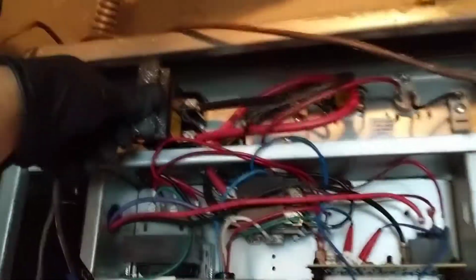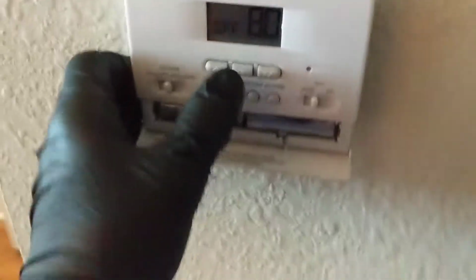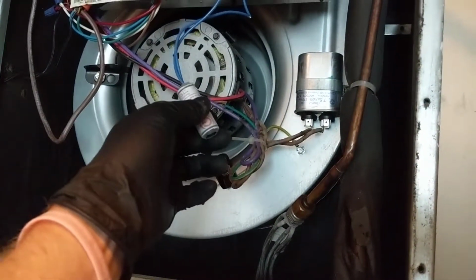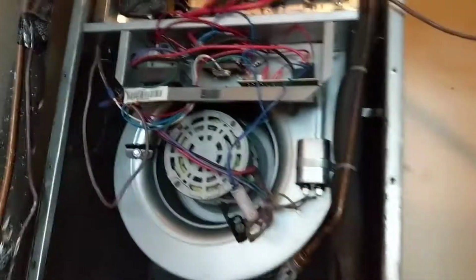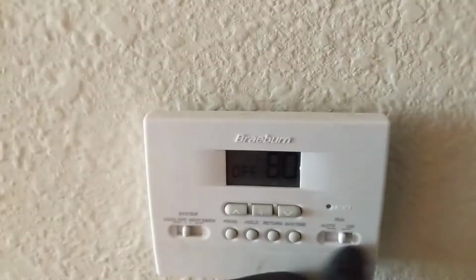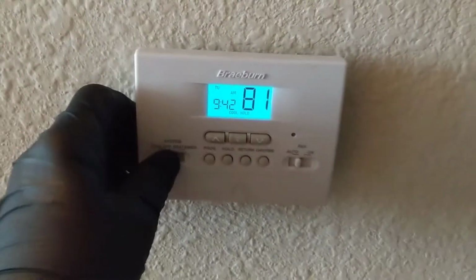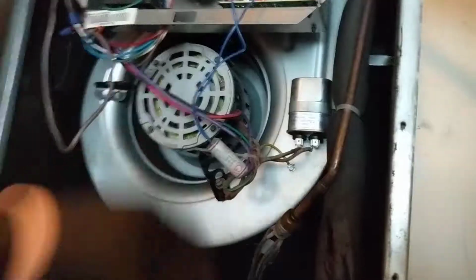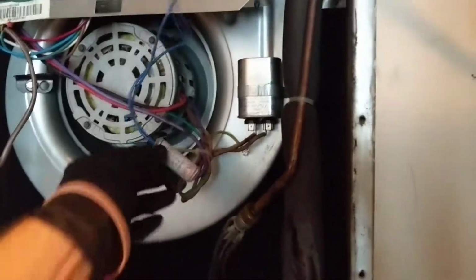Let's throw the power back in and put the thermostat back on and see what we got here. Just call the fan first. See if we get a light. No light with just the fan. Alright, so now I got it calling for cooling, fan on auto. Still no light. So it might be an intermittent short here.